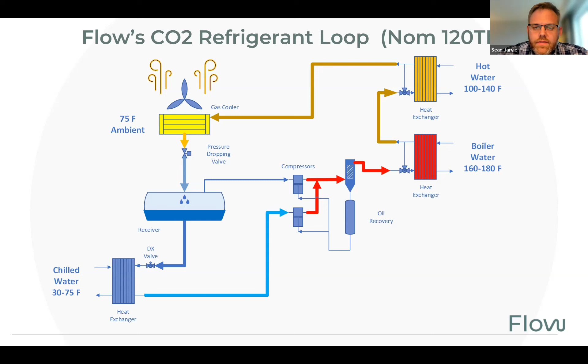Now, for the energy nerd in me, I start looking at the power of a system like this. Usually we only have a single mode of operation device, so it's either cooling or heating. But because we can use the other side of this and come up with novel uses for it — let's say we're heating sidewalks in the winter, or doing preheat of our outside air on our DOAS units, or running domestic hot water and building energy storage in the building — that's free energy. You have whatever use you want to use it for.